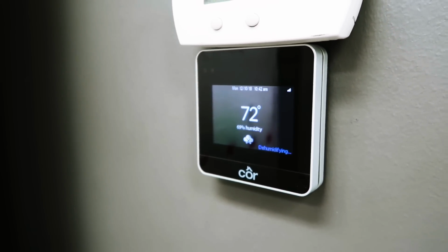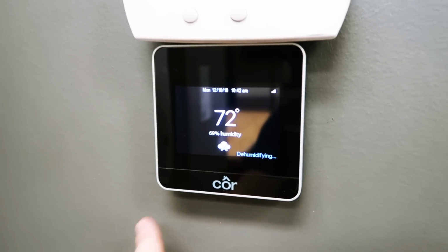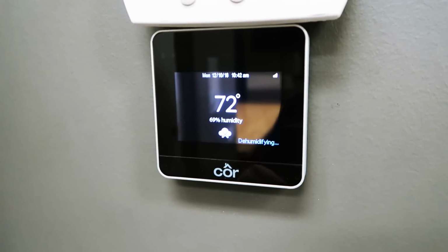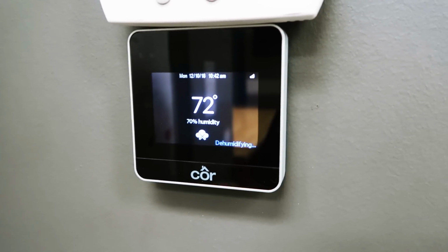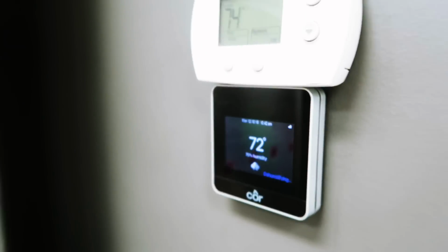So whenever you run into this where you suspect it could be generating heat internally, the first thing would be to check the amperage on all the low voltage circuits, maybe disconnect them one at a time and figure out which one's causing it. And then ultimately, in this case, it just ended up being the thermostat itself.